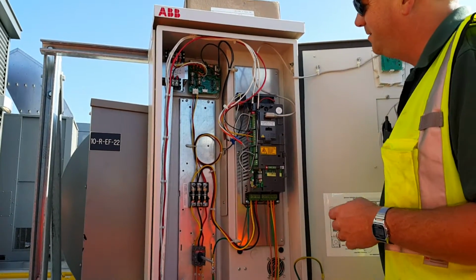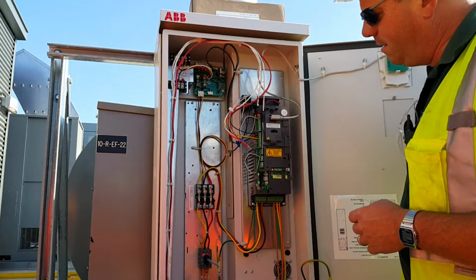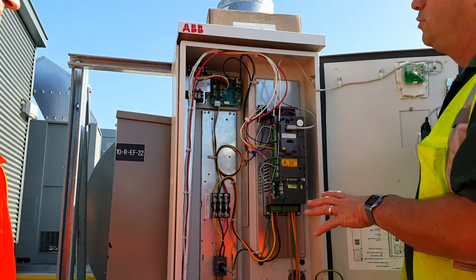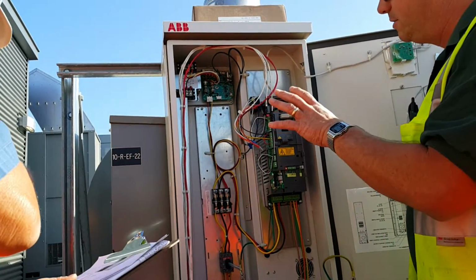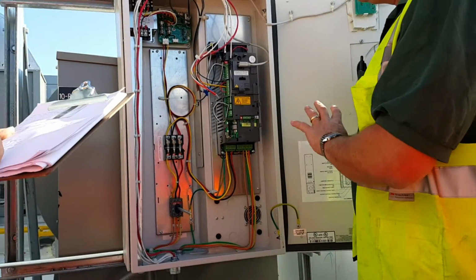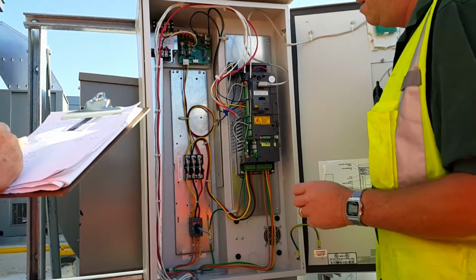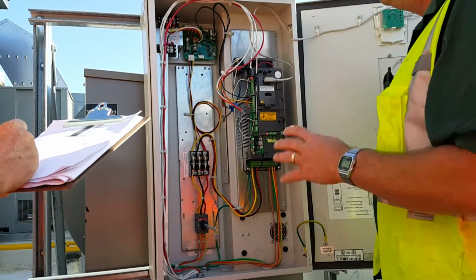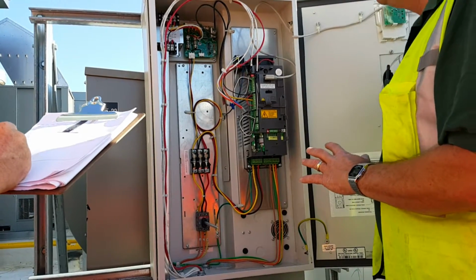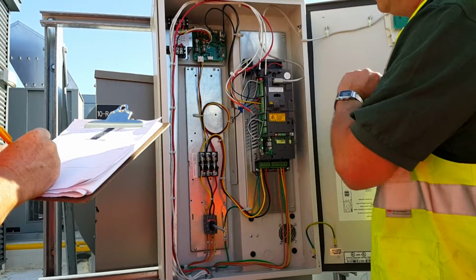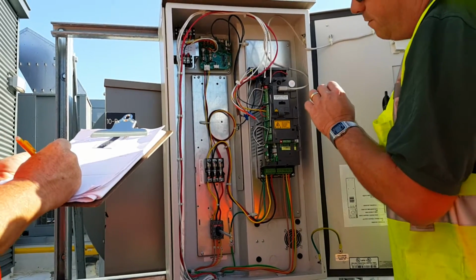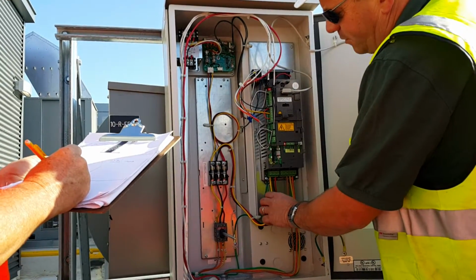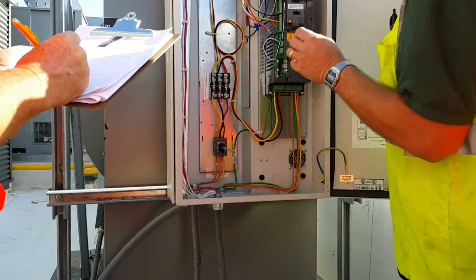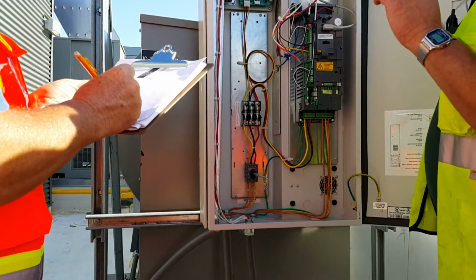It's kind of nice. A couple of maintenance items on these outdoor units. You don't have to worry as much on the indoor. But the first thing covers all of them, and that's make sure everything's tight. It's a good idea once it's run for a few months to go in there and check to make sure everything's tight. For the factory wiring like these right here, you usually don't have to worry. It's not a bad idea. It's not going to hurt it.